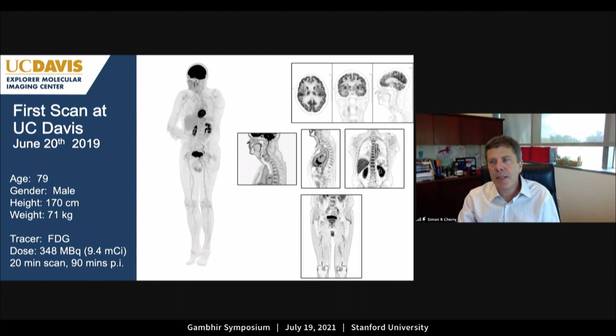So the capabilities of the system are really fourfold. It really opens up the parameter space for how we do PET studies, both clinically and in research. First of all, we can use the very high detection sensitivity to get exquisitely high quality, low noise images, as you see on the left there. There's very rich detail, very low noise, unprecedented levels of image quality for a PET scan. But because we have so much signal, we can also use that in some other ways. For example, we can image the whole body very quickly. We can get a reasonable quality whole body scan in just 30 seconds. We could also use this very high detection sensitivity to dramatically reduce the dose. On the third panel across here, you're seeing an image that has 1/20th of the regular injected dose of FDG. And again, very good image quality.